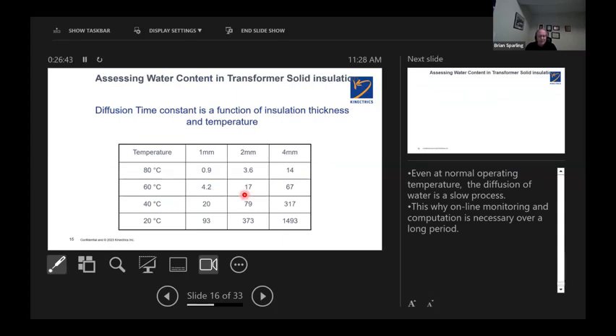Time is the other function. This is the diffusion. So there's a diffusion time constant between the oil and the paper. For 1 millimeter paper wrapped down the conductors, if you could have it at 80 degrees C for some period of time, you will reach this equilibrium point where the moisture has stopped moving between the oil and the paper. 80 degrees C, 1 millimeter paper, it's just less than a day. If the temperature is 60 degrees C, 1 millimeter paper, it takes 4.2 days. If it's 20 degrees C, it takes 93 days. That's how slow this is, and it's all a function of temperature.